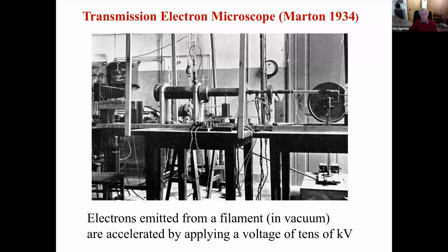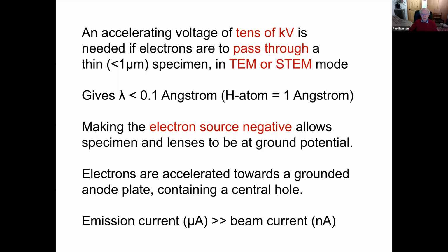So the equipment consists of the lens column, vacuum equipment to remove the air from the column, and power supplies for the lenses and for the high voltage. And if you're building a transmission electron microscope, then you have to have a specimen that's sufficiently thin, a fraction of a micron, but also you need the electrons traveling sufficiently fast to go through the specimen without absorption. And that means that you have to accelerate the electrons to a speed, a substantial fraction of the speed of light, and that requires an accelerating voltage of some tens of kilovolts.